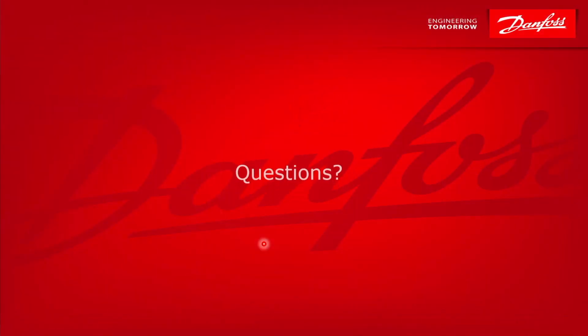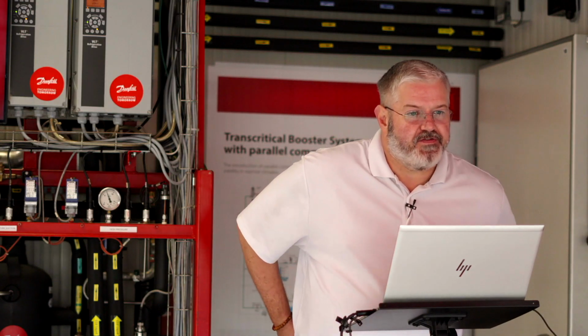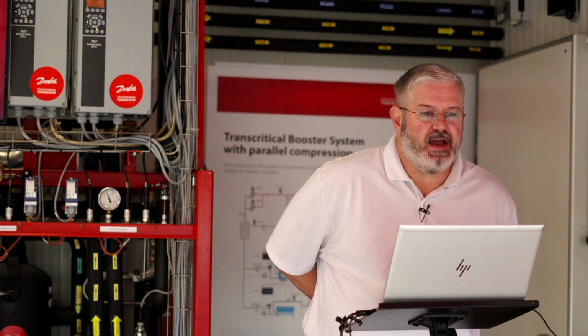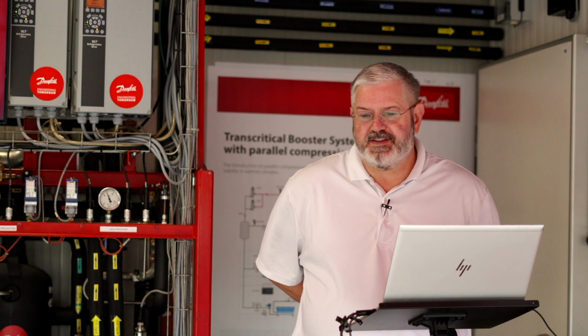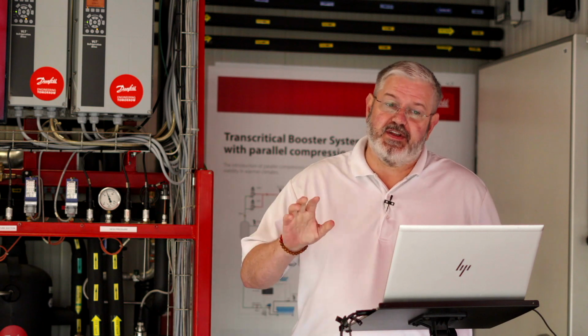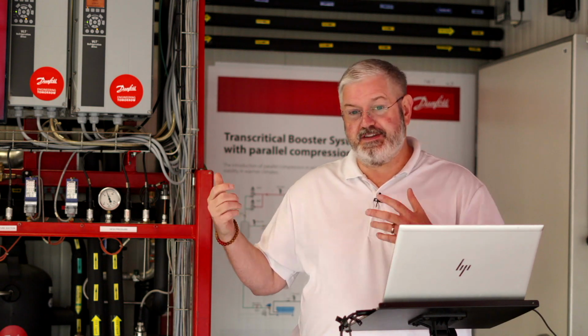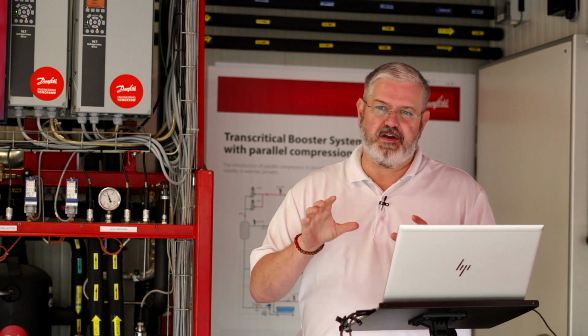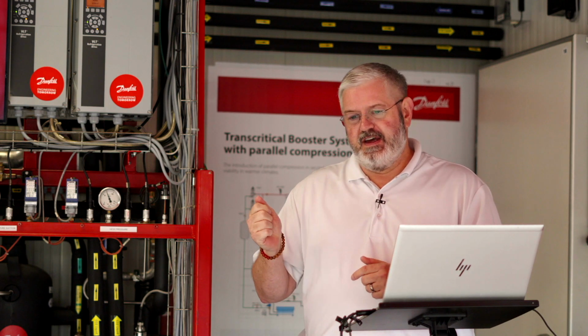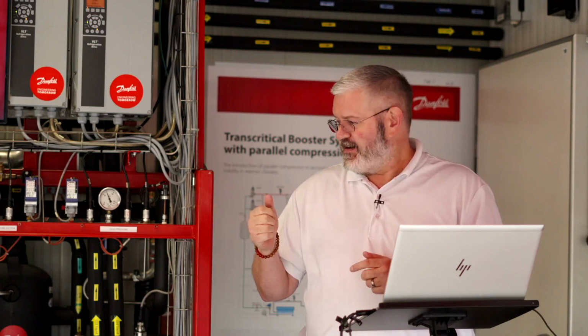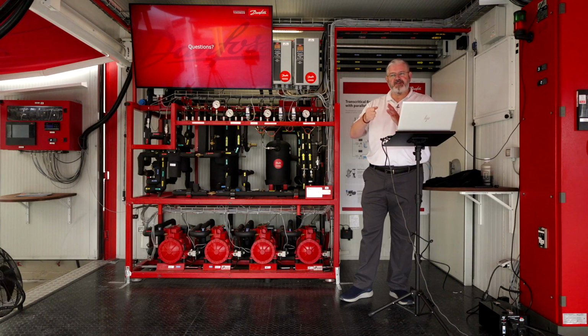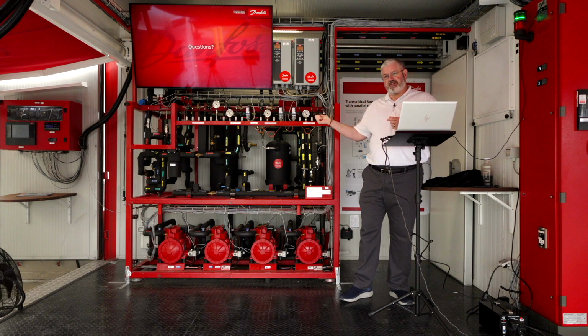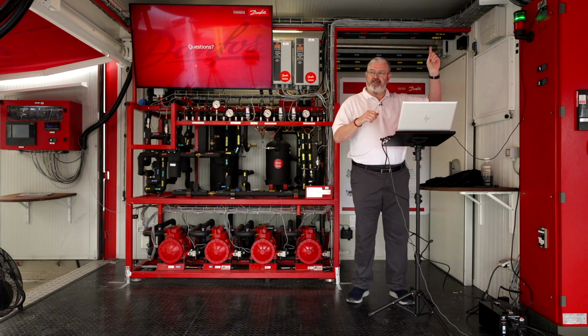So I think our next item is questions. Any thoughts of safety for the service techs? You have more components and very high pressure, so there are some safety considerations. I'll say first that I haven't personally experienced a pressure event, and I've been to dozens of the sites running these, other than sometimes you hear a relief valve chatter. You have a service valve that wasn't open, something like that, but that doesn't actually get on the service techs. That discharges into the relief header, which will be piped to outside the store.